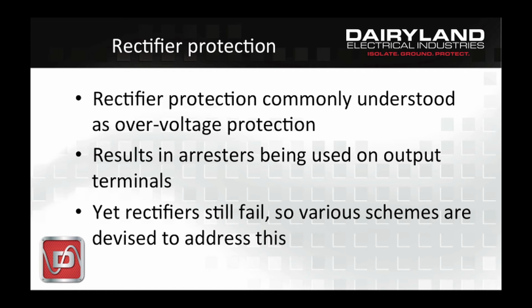Similar to equipment protection discussions, let's get more specific to rectifiers. Rectifiers are used for cathodic protection on pipelines and other structures, and in that application, they're exposed to quite the electrical elements, and they can often fail due to lightning conditions, or it could be fault conditions as well, but they generally need overvoltage protection. So commonly, arresters are used in the output terminals of the rectifier, and clearly they're meant to address, or at least attempt to address, the failure conditions. But rectifiers still fail, so obviously something is being missed.